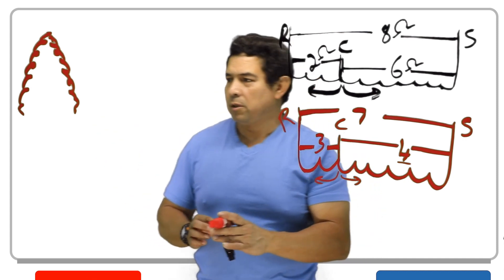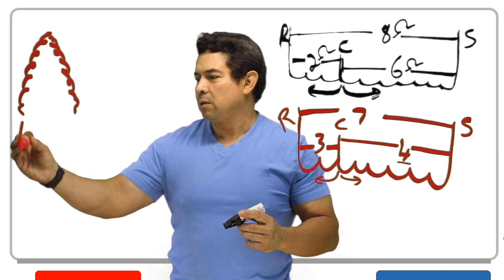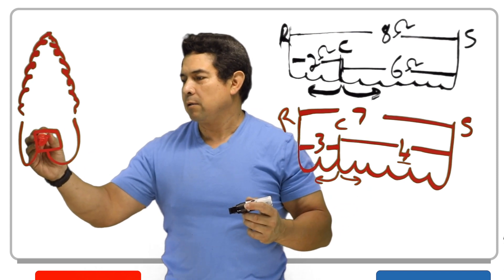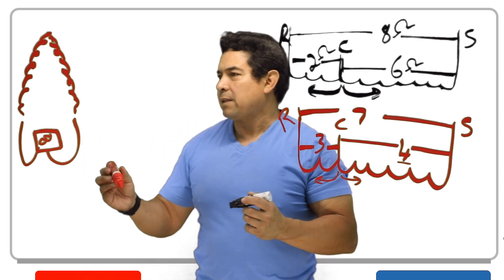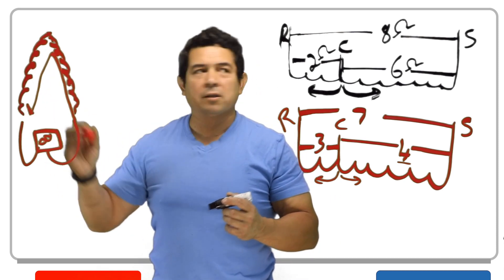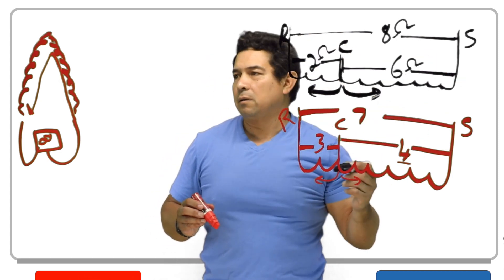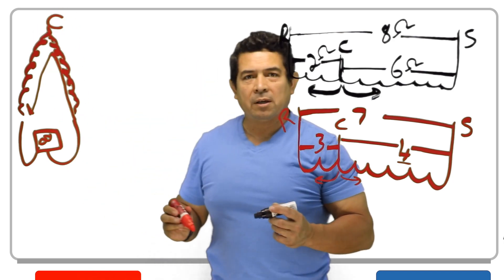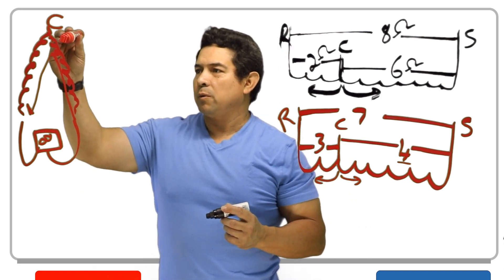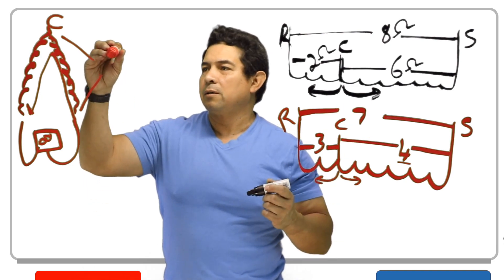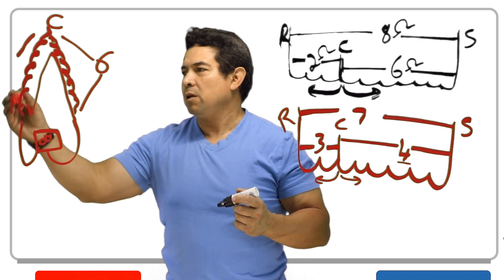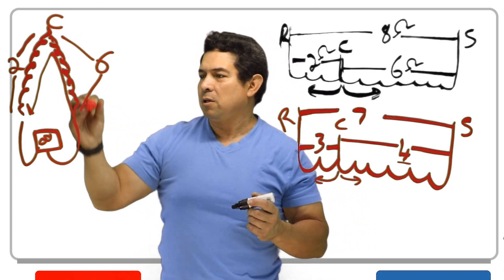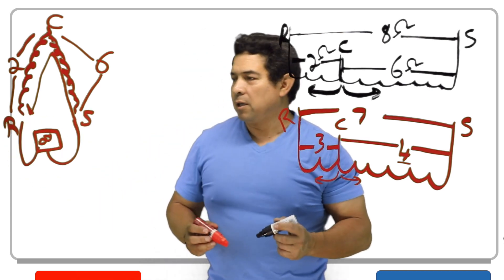If I take an ohm reading across these two terminals, I get 8 ohms total. From there, I can identify the common connection. Reading between one pair gives me 6 ohms, and between the other pair gives me 2 ohms. So this tells me that one terminal is my common connection, the 6-ohm side is my start, and the 2-ohm side is my run connection.